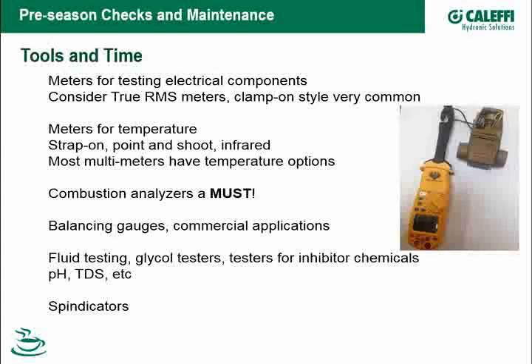Balancing gauges, you know, if you're working on commercial applications where you see a lot of flow setters that have been installed in the building, you might want to consider a delta P type of meter. They can go around and make sure that those have been set up right, or confirm that if there's been changes made in the distribution system, that somebody's gone back and readjusted those. There's digital versions out now.